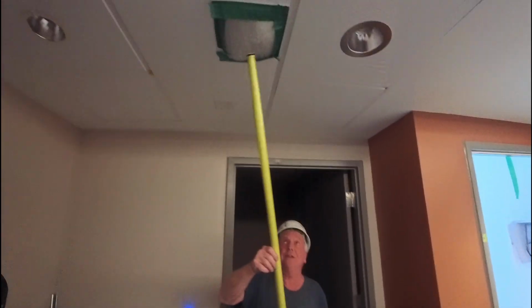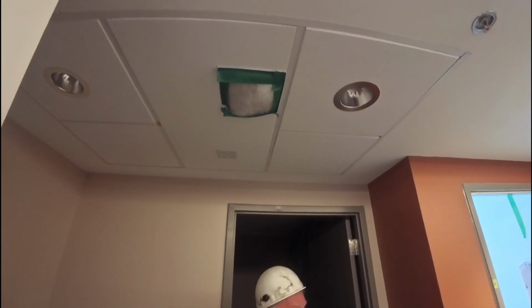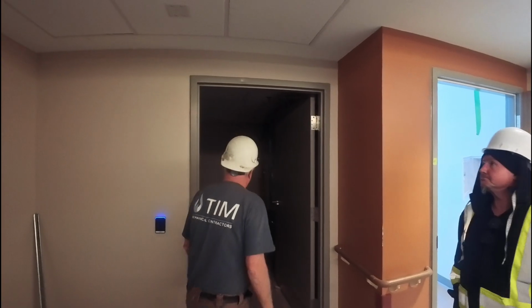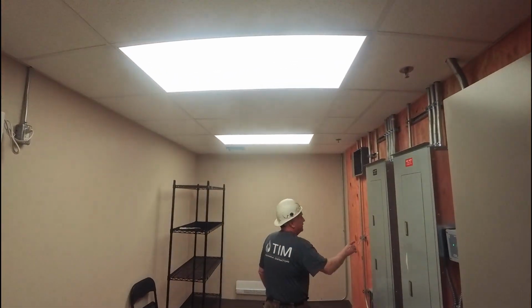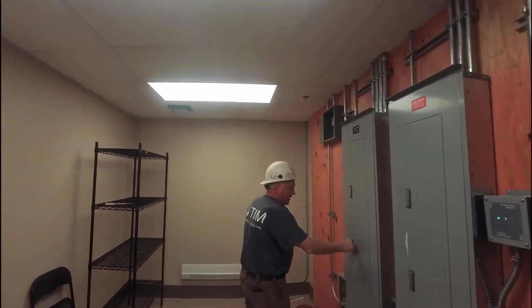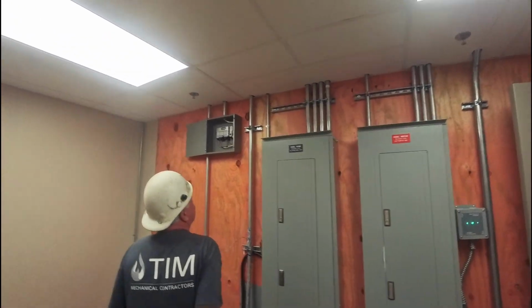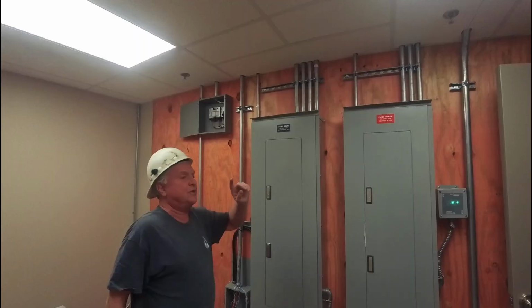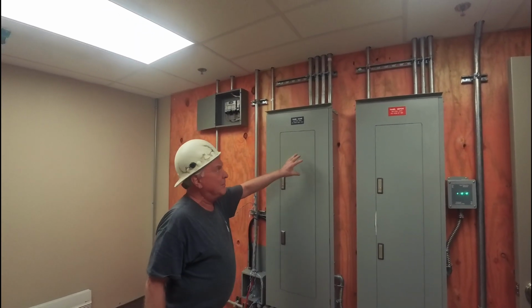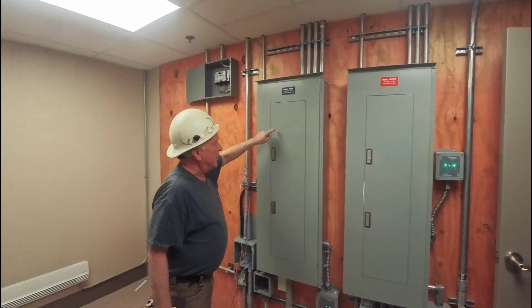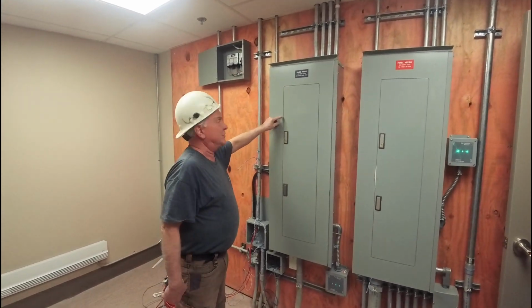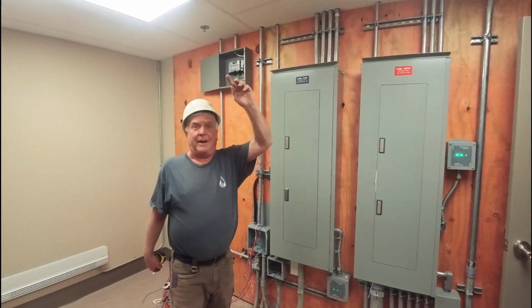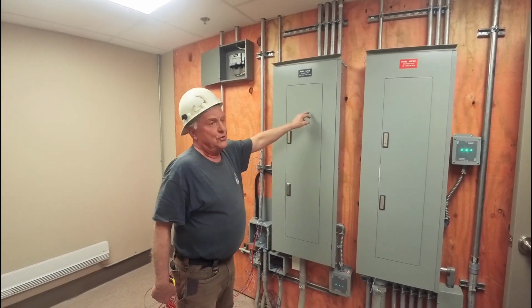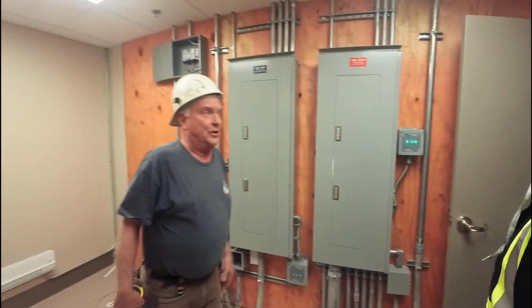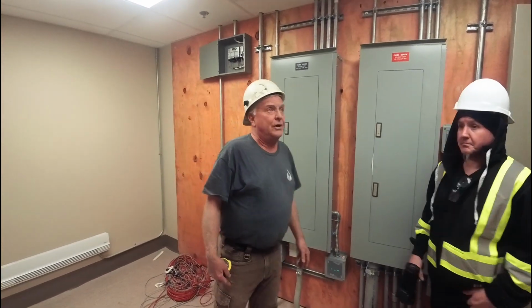Here's a grill that'll be pulling air, exhausting air out of this particular room. Here's another one. This is the electrical room. If you'd like to come in here and look, they're locked. This center panel, this is the wrong wing. It's in the B wing, but always the center panel in the B wing is where all the fire damper breaker is located. It operates all the fire dampers in this particular wing. It's usually number 8 and number 9. Just for your information, but you get that through the electrician walk through.